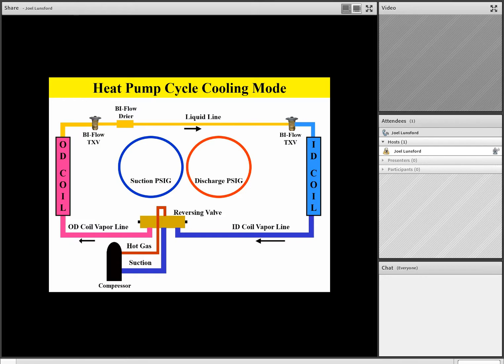Again, we're going to point out that if the outdoor coil is red, that means it's hot, so we're in the cooling mode. If the indoor coil is blue in this case, that means it's cold. Now when we reverse cycle, we'll see that the indoor coil becomes hot in the heating mode of operation on a heat pump, and the outdoor coil becomes cold. Now team, remember, this is an important concept: a heat pump allows us to heat and cool the conditioned space with the refrigeration cycle.